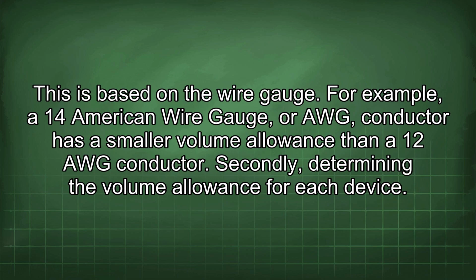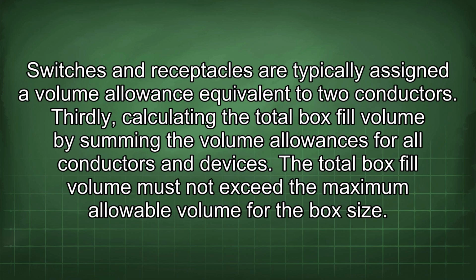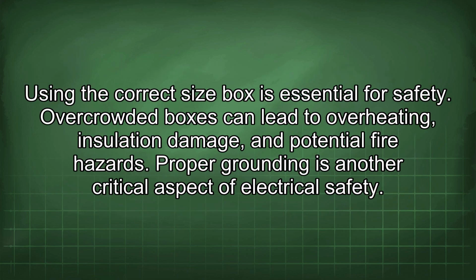This is based on the wire gauge. For example, a 14 American wire gauge, or AWG, conductor has a smaller volume allowance than a 12 AWG conductor. Secondly, determining the volume allowance for each device. Switches and receptacles are typically assigned a volume allowance equivalent to 2 conductors. Thirdly, calculating the total box fill volume by summing the volume allowances for all conductors and devices. The total box fill volume must not exceed the maximum allowable volume for the box size. Using the correct size box is essential for safety. Overcrowded boxes can lead to overheating, insulation damage, and potential fire hazards.